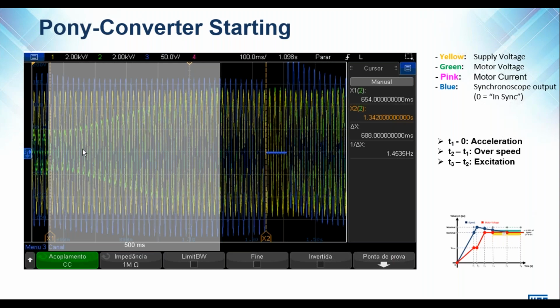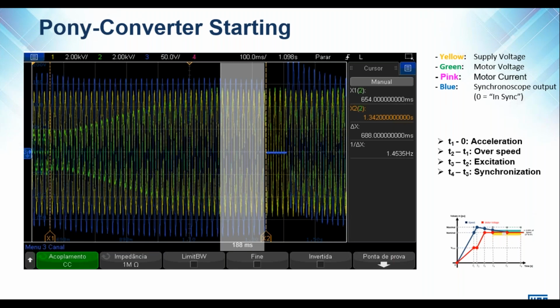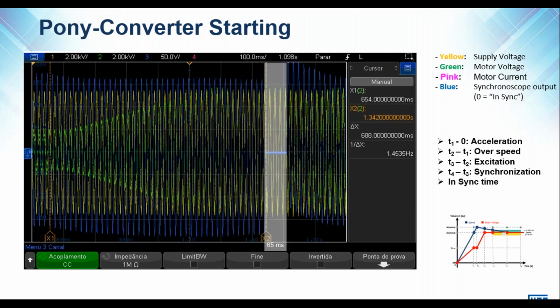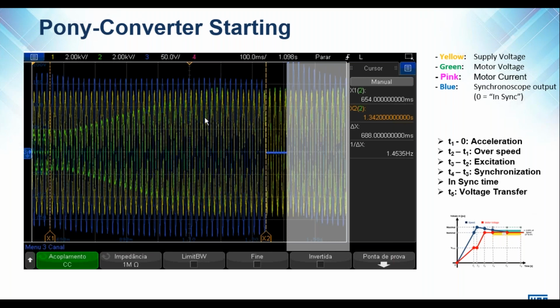Then we move to the second phase, where we remove the VSD from the circuit, but use the excitation control to increase the voltage of the motor. That is why the green voltage is increasing to meet the supply voltage rating. Then we are searching for synchronism between the supply voltage and the motor voltage. And at this point, synchronism has been obtained, and we can close the bypass switch.